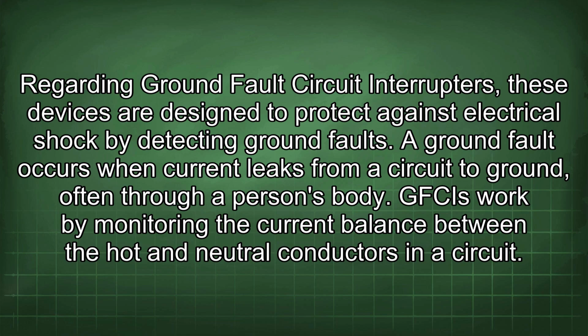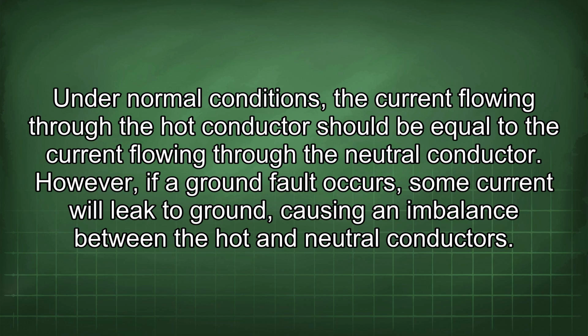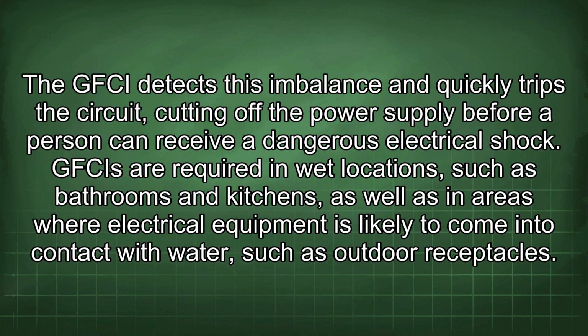Regarding ground fault circuit interrupters, these devices are designed to protect against electrical shock by detecting ground faults. A ground fault occurs when current leaks from a circuit to ground, often through a person's body. GFCIs work by monitoring the current balance between the hot and neutral conductors in a circuit. Under normal conditions, the current flowing through the hot conductor should be equal to the current flowing through the neutral conductor. However, if a ground fault occurs, some current will leak to ground, causing an imbalance between the hot and neutral conductors. The GFCI detects this imbalance and quickly trips the circuit, cutting off the power supply before a person can receive a dangerous electrical shock.